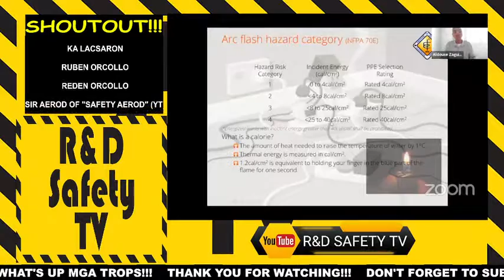And the categories 1, 2, 3, 4, here they are on the next slide. Okay? So you see here the incident energy: the lowest, category 1, is only from 0 to 4, then greater than 4 to 8, greater than 8 to 25 cal. Now, beyond 40 cal, it is still possible, especially if the person is working on transmission lines. And there are PPEs rated up to 100 cal. However, we don't recommend it. We only want you to look up to category 4.